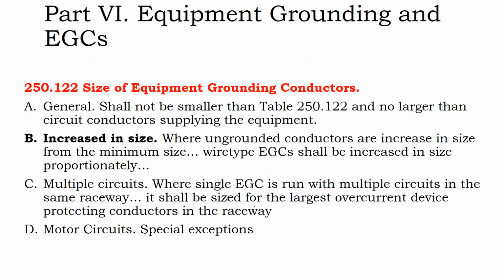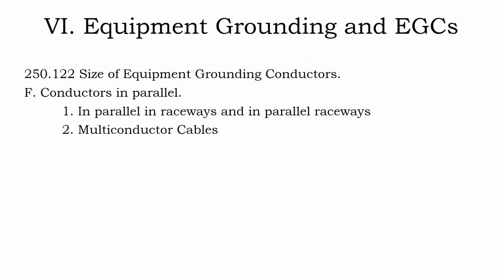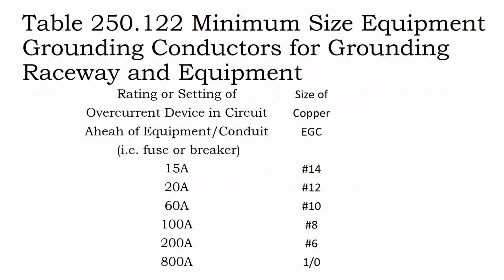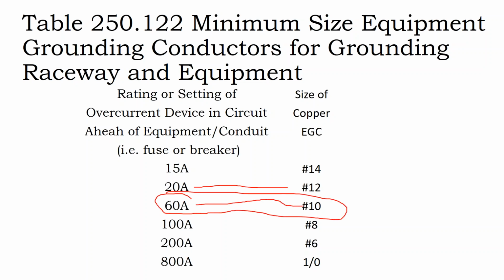Let's kind of move away from the grounding issues. So we get to this table 250-122, the minimum size of the equipment ground conductors, and it's basically just based off fuse sizes. The solar inverters, like microinverters, are 20 amp circuits, and then most battery and residential solar inverters are up in the 60 amp circuit. And so you get this number 10, and you're often buying number 10 as your solar cable.